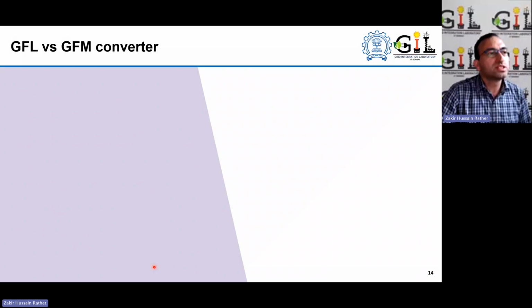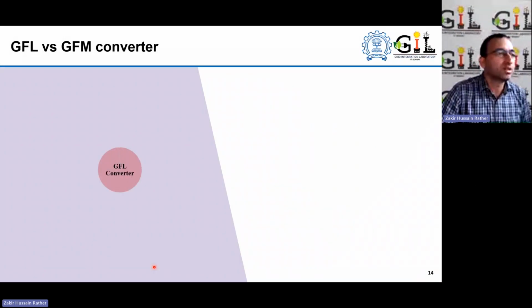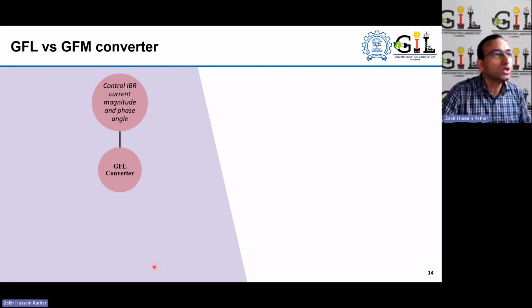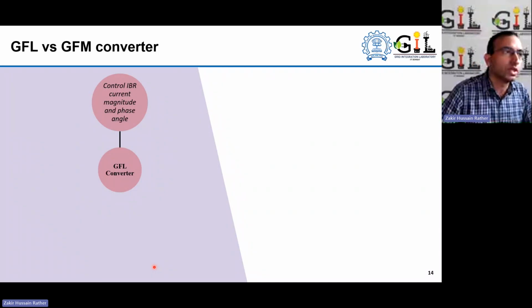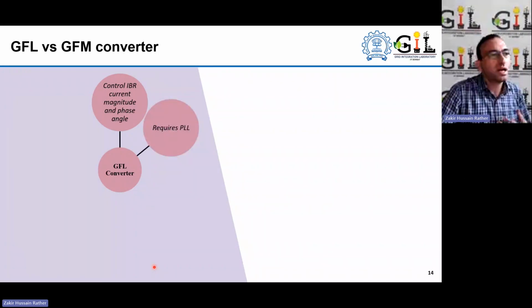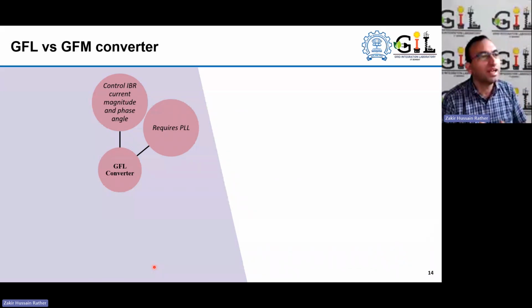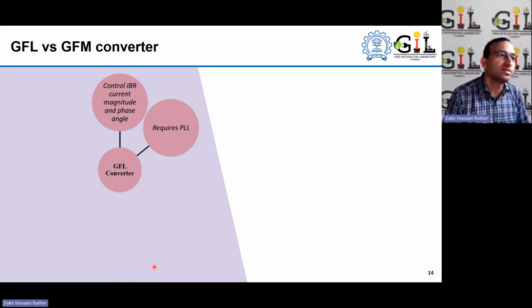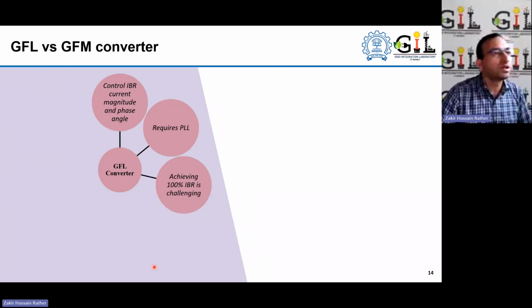Now, what are the major differences in terms of functionalities or capabilities between grid following and grid forming technology? GFL technology is able to control the current magnitude at its terminal. It does need a PLL for synchronization, and it needs the PLL throughout its operation. So it's not that we synchronize the inverter with the grid and then that's done, the way we do in the conventional generator. Here you continuously need the PLL, which keeps the inverter synchronized with the grid. There are several issues with the PLL, particularly during transients, that introduce additional challenges with grid following technology.